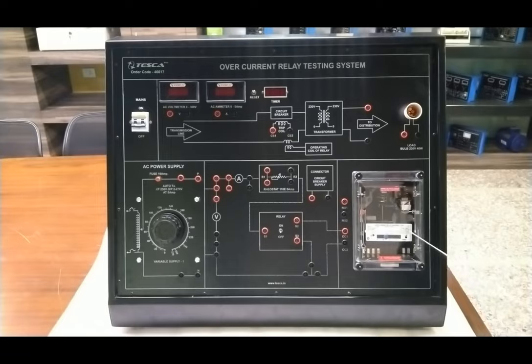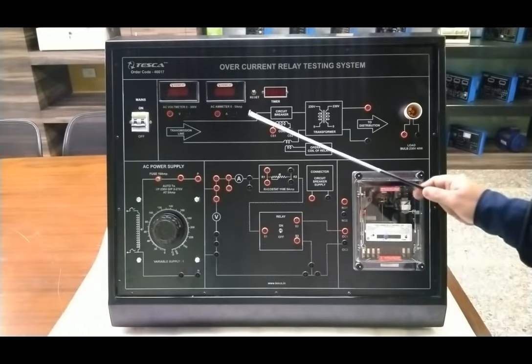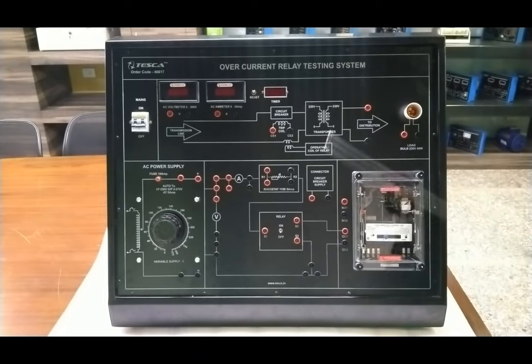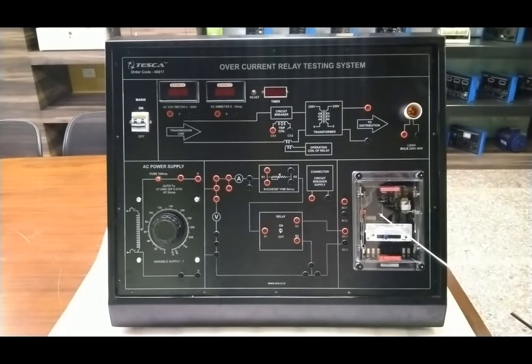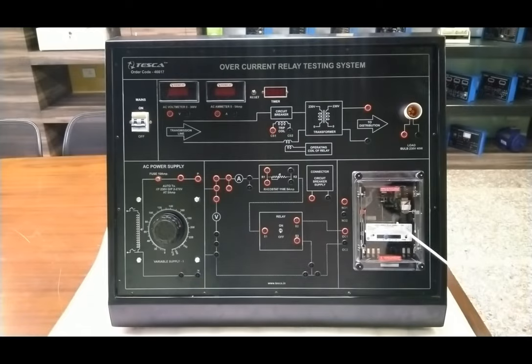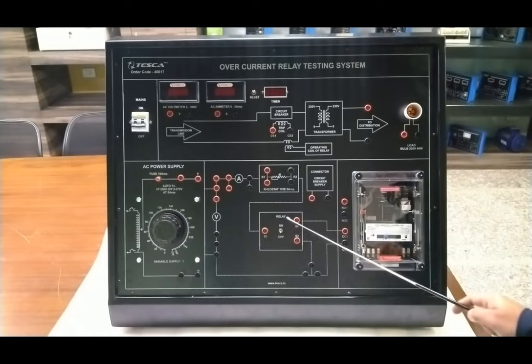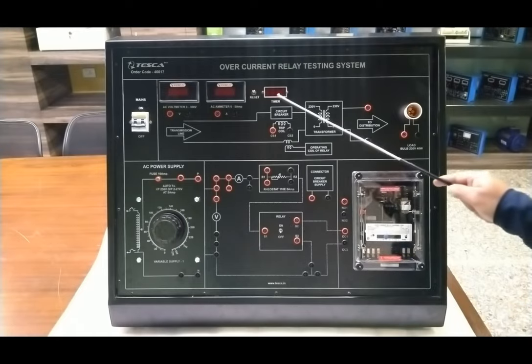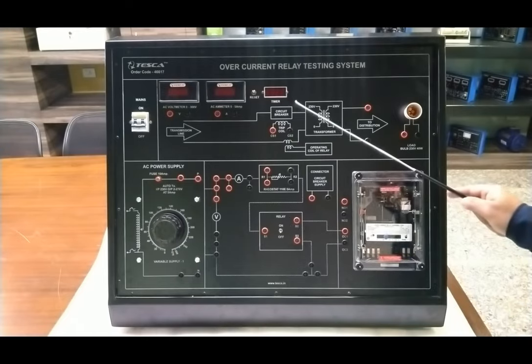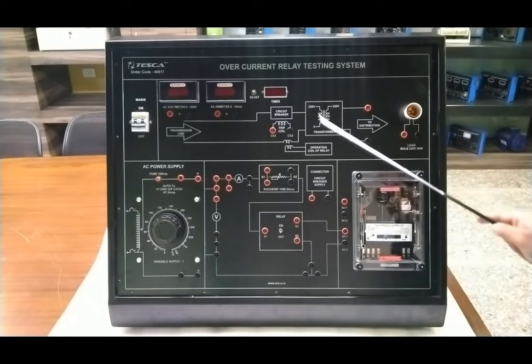We can set the value according to the current value setup of the overcurrent relay. The current will be seen on the AC ammeter and we will set the current using the rheostat to the appropriate value. Then we will see when the current starts picking up — as the relay starts picking up, we will turn on the timer with this on/off switch provided here, so that the time of the tripping will be noted down on the timer.